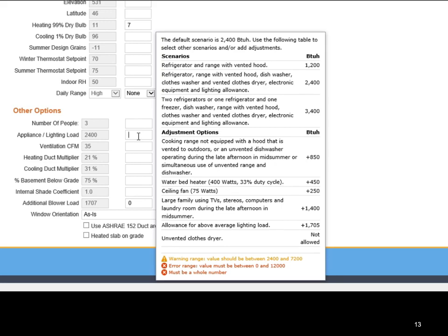If you have a lot of internal gain, say somebody with an aquarium, or somebody with a commercial kitchen in the house, you should consider it at that point. One thing I will point out is that appliances have gotten newer. The amount of waste heat that they contribute to the house has gotten smaller. And this has a pretty big impact on cooling, as I recall.